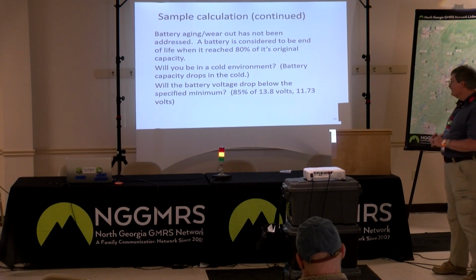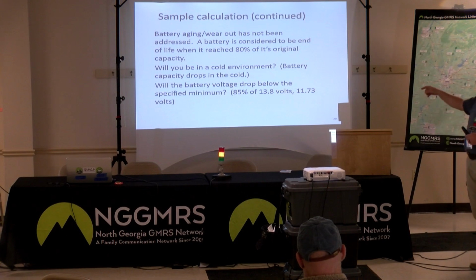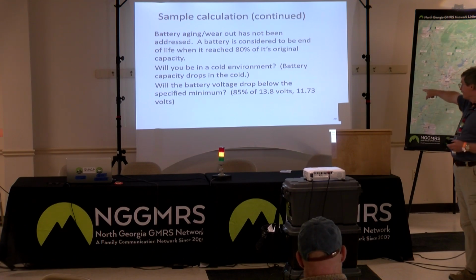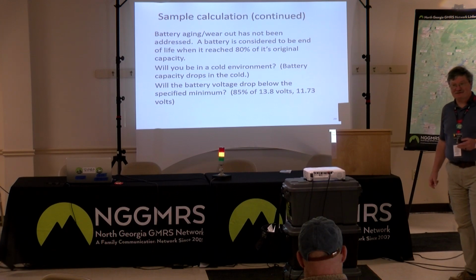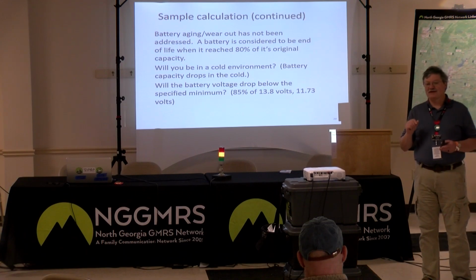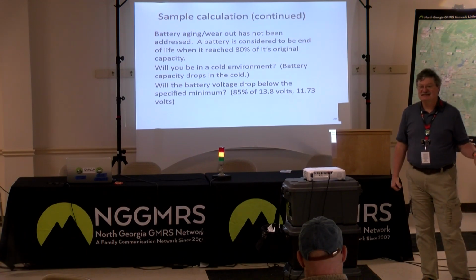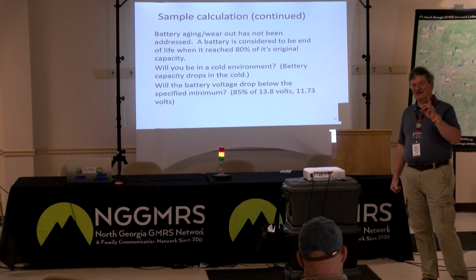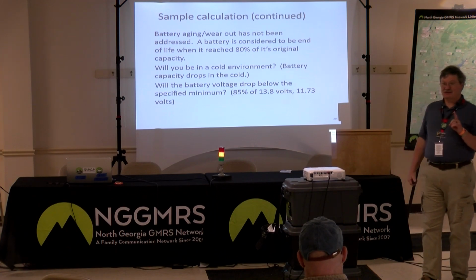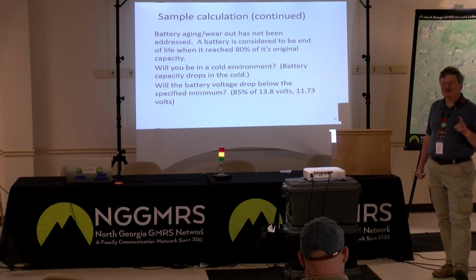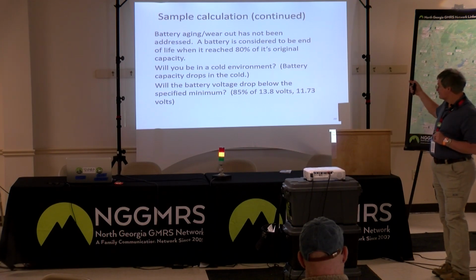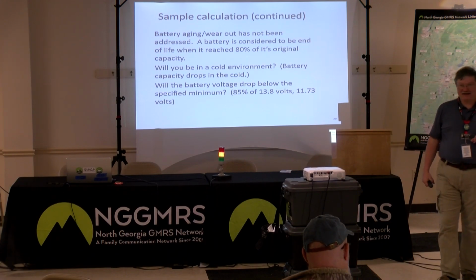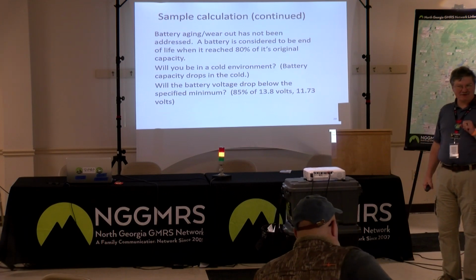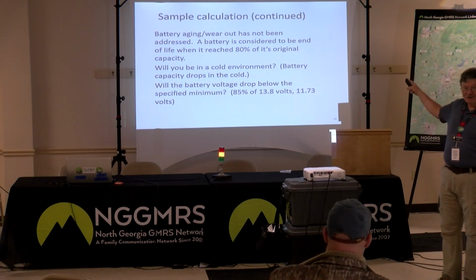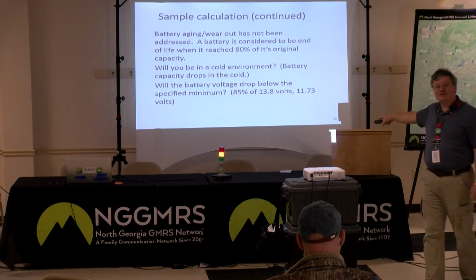What is the minimum battery voltage drop that you can tolerate? If you remember back, that Yaesu radio, 13.8 volts plus or minus 15%, that's 11.73 volts. The lead acid battery people rate their batteries on amp hours to go to 10.5 volts. So, I need to correct that. And you have to work with the battery manufacturer's information to determine how much correction you need. So, in this case, I would say a 120 ampere, 125 ampere hour battery might be okay, provided that load, that radio, would tolerate the lower voltage.